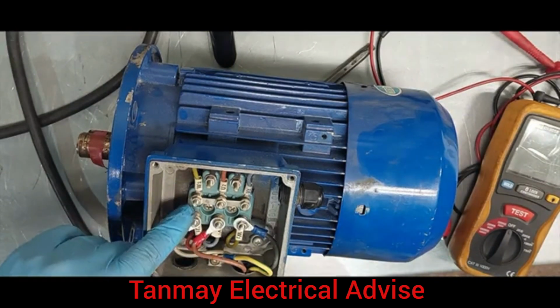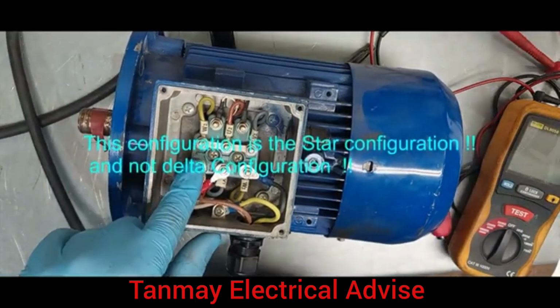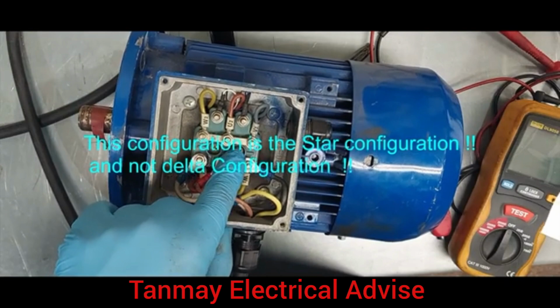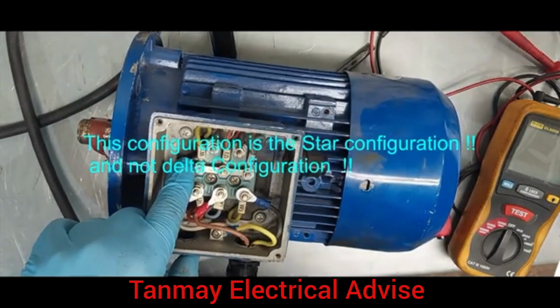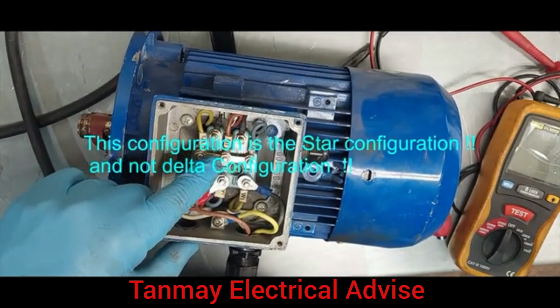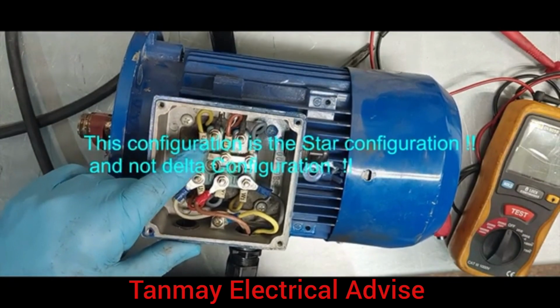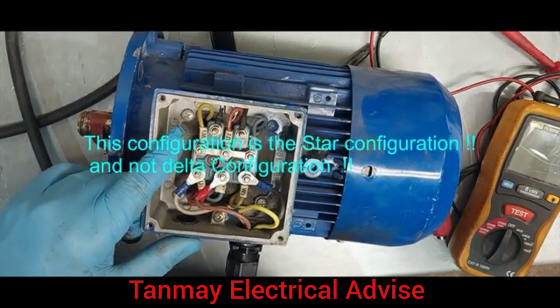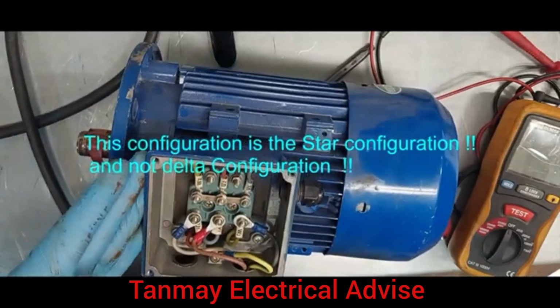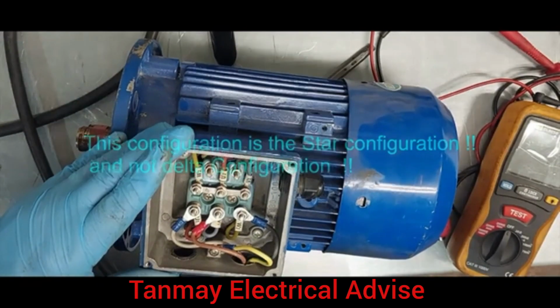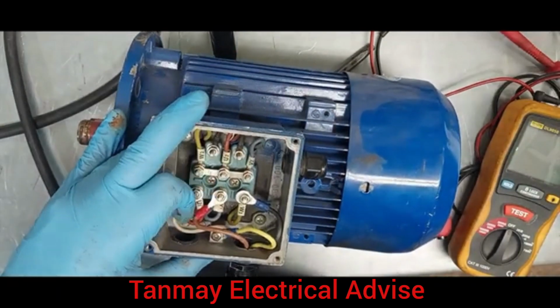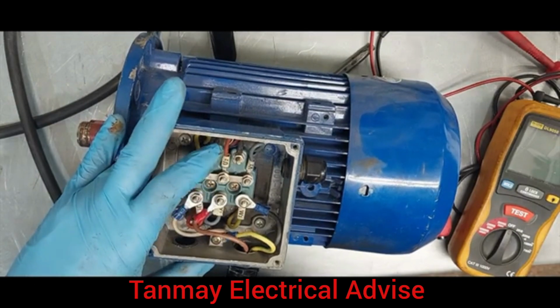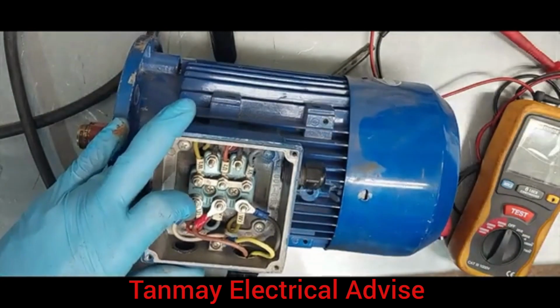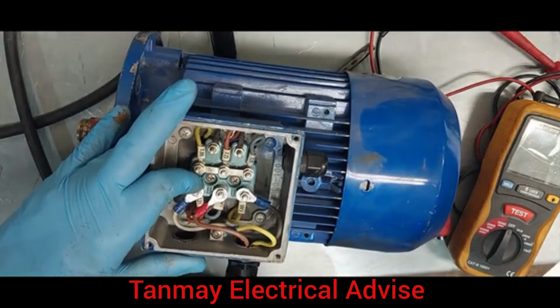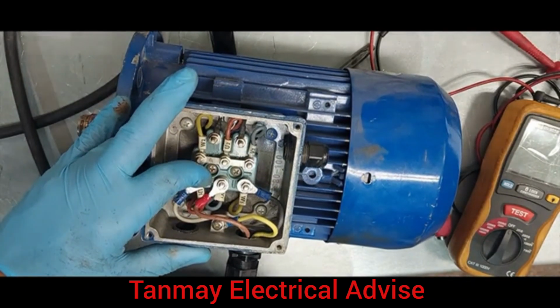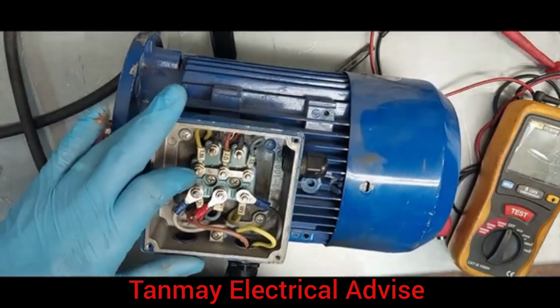In order to check these parameters very well, this motor is connected in delta. We have to remove this delta connection so that we can check the individual windings. And we have to check if there's an open loop. We'll see that there's a very high resistance on the winding. If the resistance reading is very high, we know that there's a problem with the winding of the motor. Otherwise, it's supposed to give us low resistance, around 0.1 ohms. So we can start by doing this.